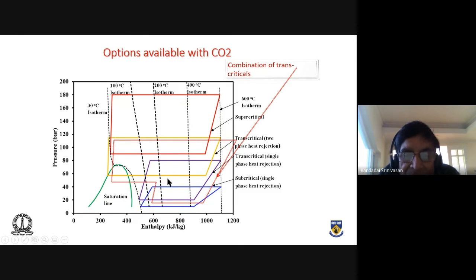In addition, we also have a combined cycle, which is Rankine, trans, and everything together, with quite a bit operating under subcritical. Part of the compression takes place in the compressor. The compressor takes a substantial amount of work from the turbine. The enthalpy change from the turbine is significant, but this is what the turbine gives, and this is what the compressor takes. So what you get coming out, which you can sell and make money from, is the difference between the two, and that's actually quite small here.